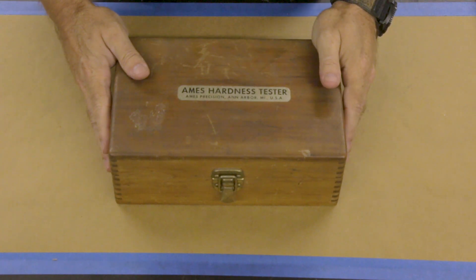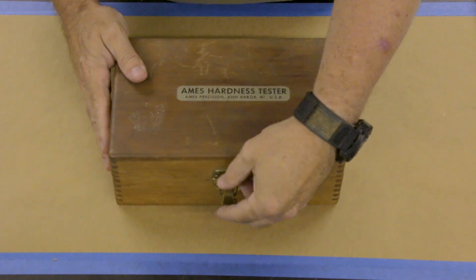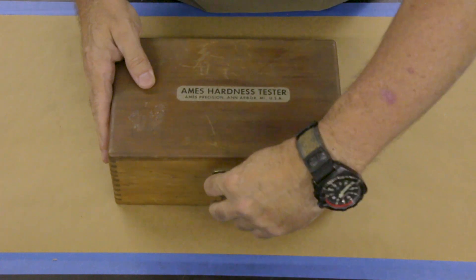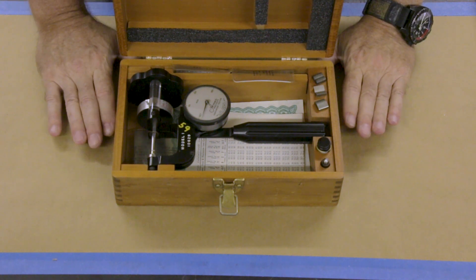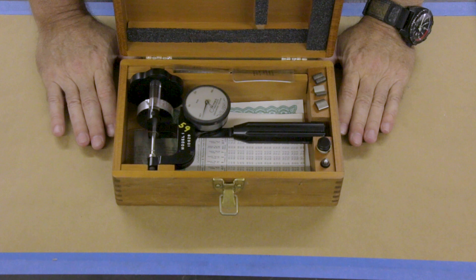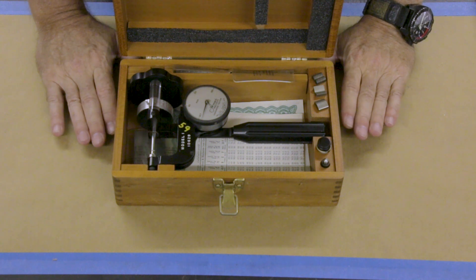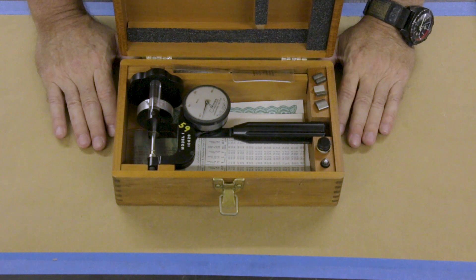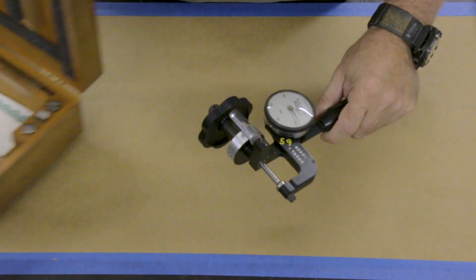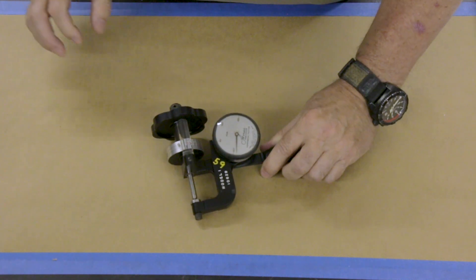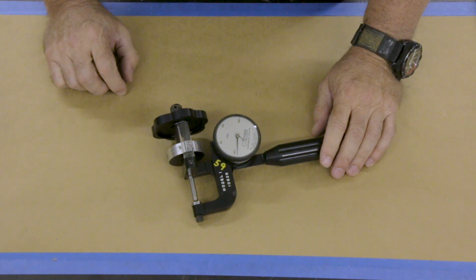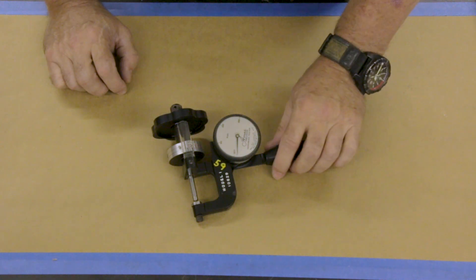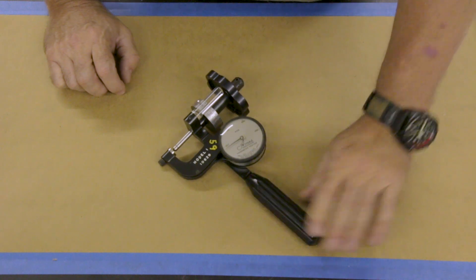Alright, so this is the Ames Model 1 Hardness Tester. What this is, is a portable professional tester designed for use on materials that cannot be brought to the bench for testing. Its level of accuracy is as good as a high quality bench tester and it's better than most import testers. Ames still manufactures these testers and they do offer repair and calibration services for them.